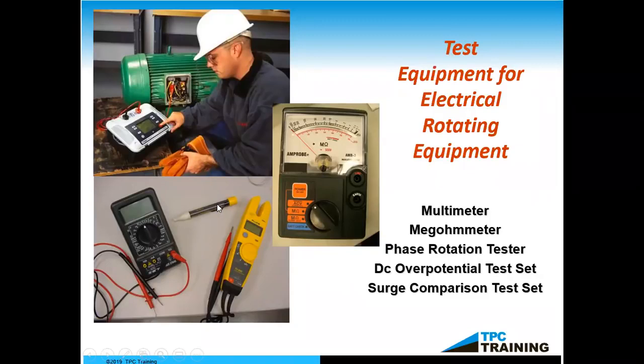Just to the left of the multimeter, we see a little pen tester, and I can tell you that the pen tester also works off the theory of that changing magnetic field. So it works off induction, just like the motor works off it. So we've got to be careful with the pen tester, because if there is just stored energy, for instance a capacitor, then that pen tester might not pick it up. So we've got to be careful with the pen tester. It's good for a quick check, but much better to put the multimeter on that circuit.